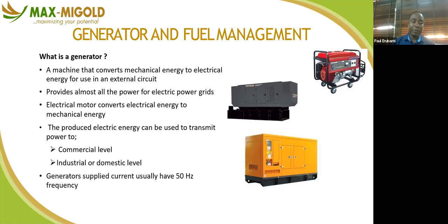So generators also operate and supply at a specific frequency, usually 50 hertz. If your generator is supplying above this value, there is a problem. But there is a tolerance. As I told you earlier on, we have between 49 and 52. Anything outside this is out of phase, so your appliance will not work. So you may be spending more on fixing your appliance. That's why you need to keep a record of what your machine is producing, or how your facilities are run.